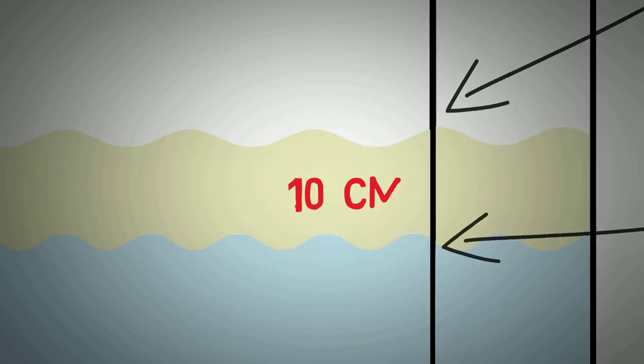Usually around 10 centimeters differential in process fluids is needed for the instrument to differentiate between the two process fluids, but some top of the line equipment can measure down to five centimeter interfaces.